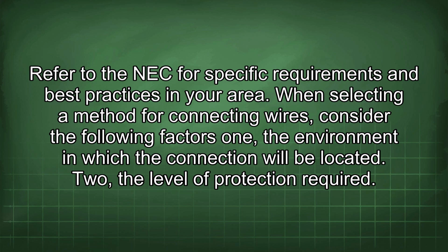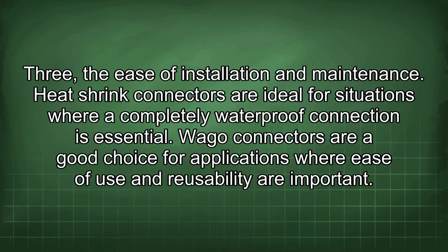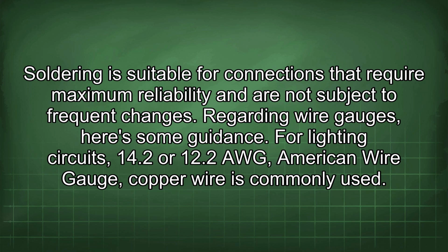When selecting a method for connecting wires, consider the following factors. 1. The environment in which the connection will be located. 2. The level of protection required. 3. The ease of installation and maintenance. Heat shrink connectors are ideal for situations where a completely waterproof connection is essential. Wago connectors are a good choice for applications where ease of use and reusability are important. Soldering is suitable for connections that require maximum reliability and are not subject to frequent changes.